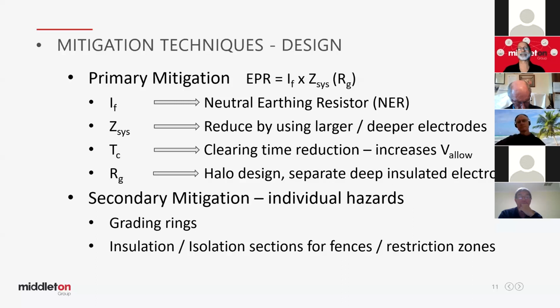There are two mitigation techniques. We can call them primary mitigation and secondary mitigation. Primary mitigation is the steps we take to reduce the earth potential rise. If we reduce the earth potential rise, any touch voltages that we've noticed on fences and transfers will be reduced in proportion to the reduction in the earth potential rise. So here's something we can do to reduce the EPR, one thing, and we affect all of the other hazards in proportion. We can bring them all down at one time.